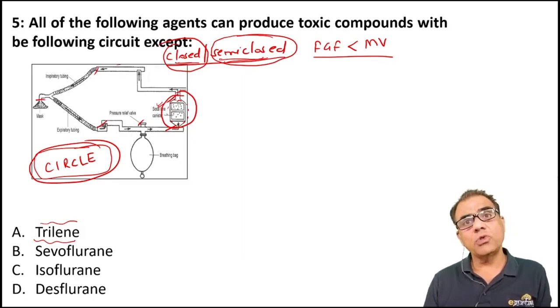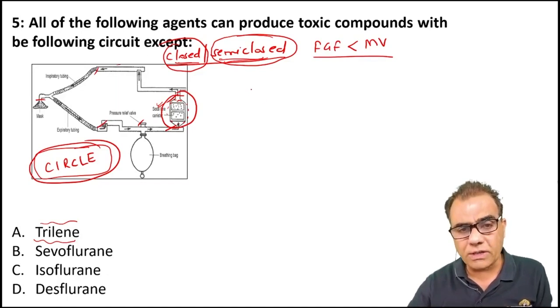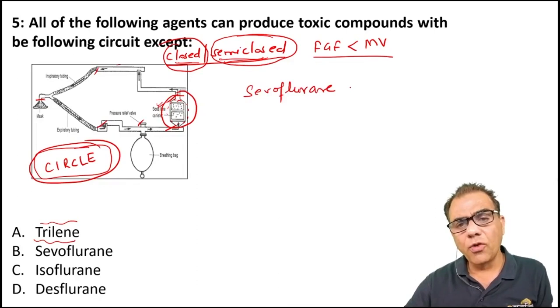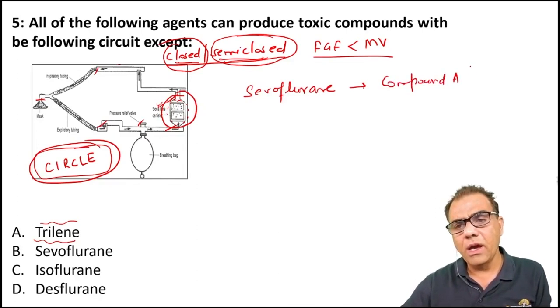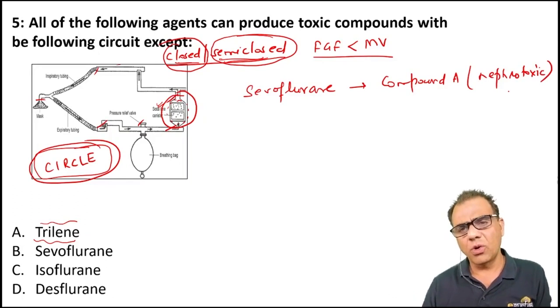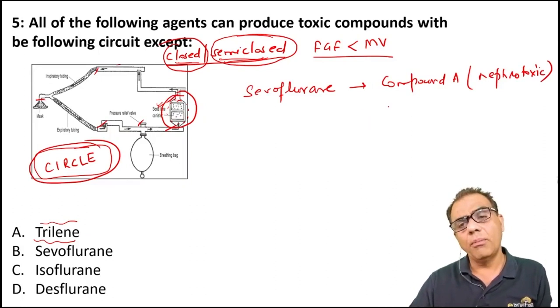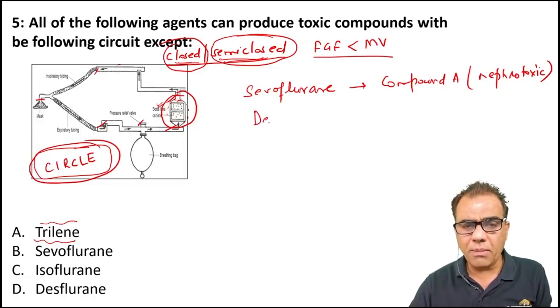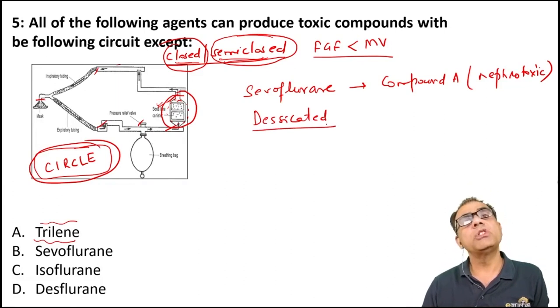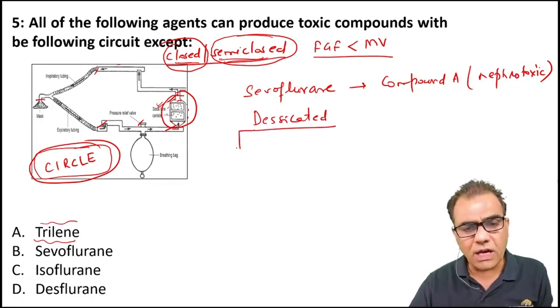But the agents which we are using nowadays can also react with soda lime to produce toxic compounds. For example, sevoflurane, by reacting with soda lime, can produce a toxic compound called compound A, which is nephrotoxic. Although the production of compound A is very rare, nowadays more or less a theoretical phenomenon, yes, it can produce compound A. Then there is a problem if soda lime becomes desiccated. Desiccated means dry. Then it can really cause havoc.